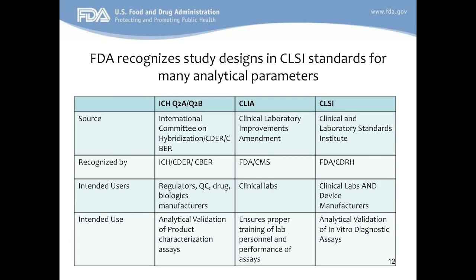One of the questions that we often get, particularly about analytical validation of in vitro diagnostic devices and determining analytical performance, is about acceptance criteria, and how the device developer knows what acceptance criteria are okay for their particular device. A simple example of acceptance criteria would be, when looking at the precision and reproducibility of the device, what's an acceptable percent coefficient of variation, or percent CV, when measuring the same sample over and over again. There are acceptance criteria for all of the analytical performance testing that is done, but that's just one example. The challenge here is that the acceptance criteria and study design depend on the type of the device, the technology behind the device, and also the intended use.